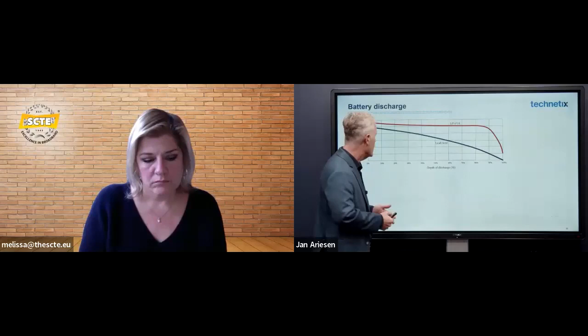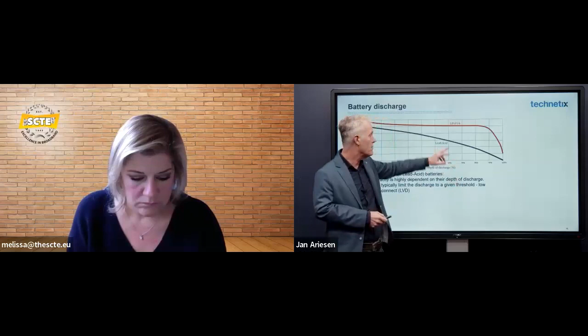This makes it very critical. Lead acid batteries are very sensitive to discharging. The further you discharge, the shorter the lifetime of the battery. You can see the cycle capacity is highly dependent on the depth of discharge, that's what you have with lead acid batteries. So operators typically say, okay, if it gets below this level, I just stop, I cut the loading here.